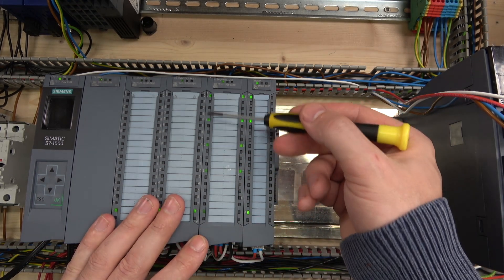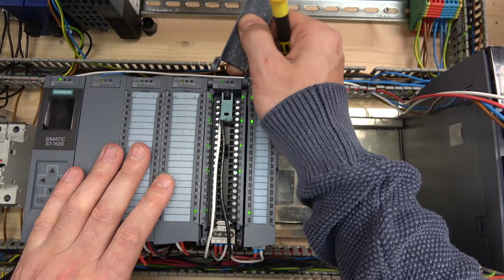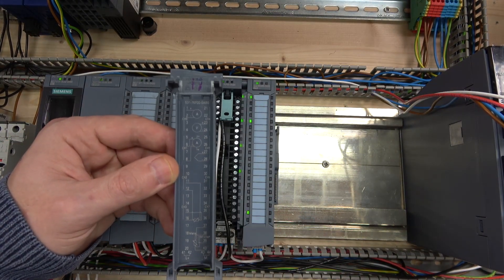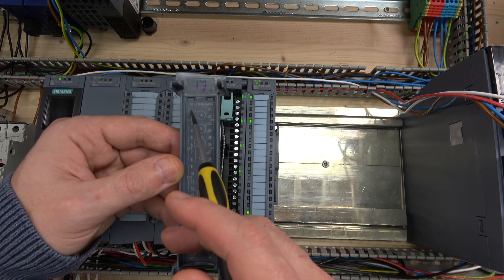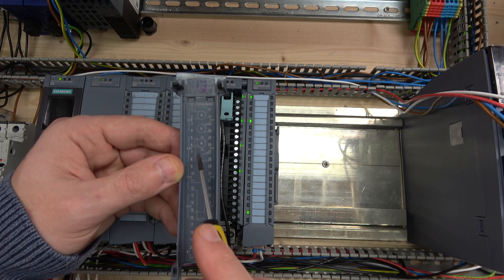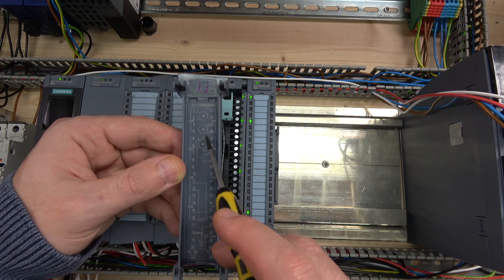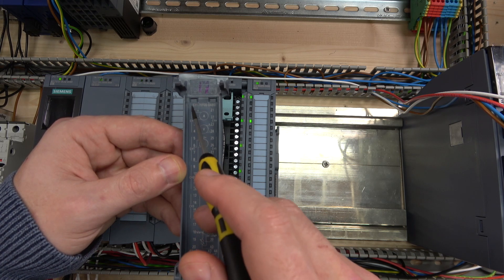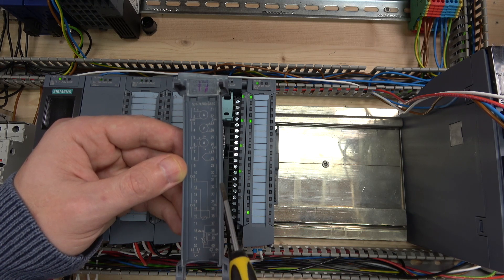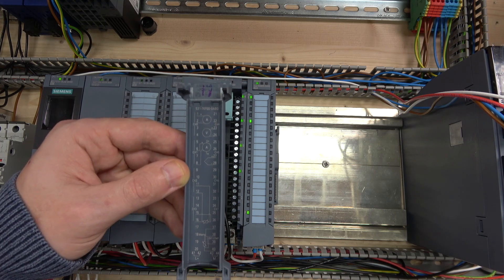The card has zero to eight channels — that's zero to seven, meaning eight channels total. If you pull off the lid, Siemens has been kind enough to illustrate how each particular sensor type would be wired. For milliamps, you can see the two-wire wiring diagram. There is a manual which I'll leave in the description below covering all the necessary wiring. As you can see, the four-wire diagram shows my sensor receiving its own power and outputting plus and minus to the card.